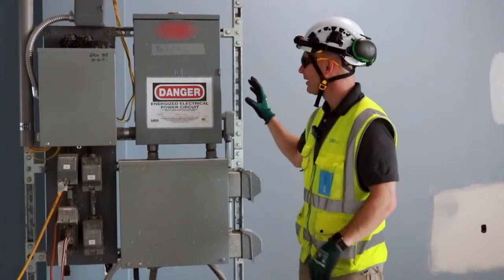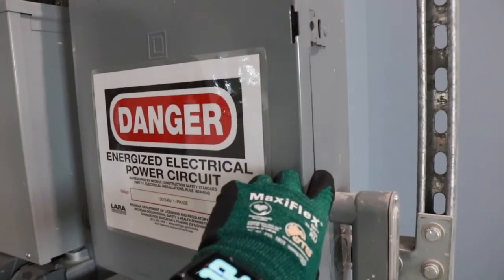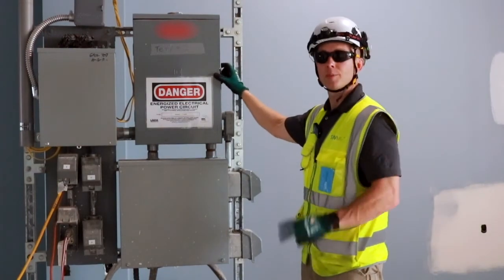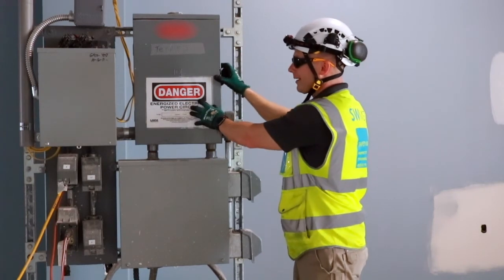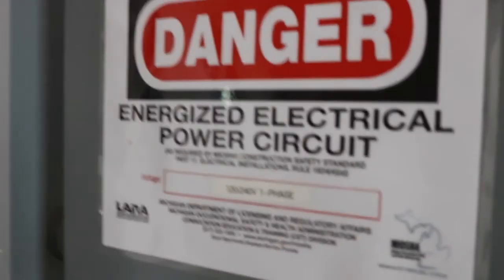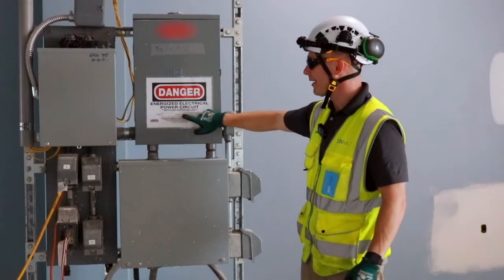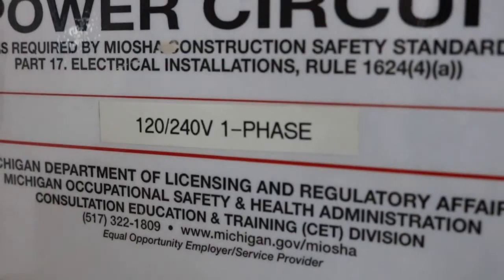Practice number one, each panel has an outer cover on it. These guys did a great job putting that on. Practice two, they've identified an accident prevention sign by putting it on the outer cover. Practice three, they've included the voltage of the panel.